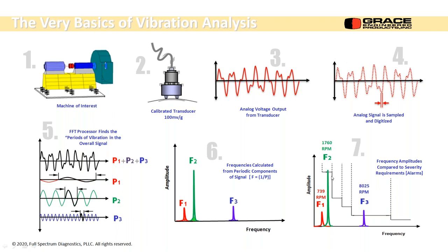If I know where 1 times RPM is, I can make my stair step pattern. And this we talked about a little bit last Thursday. This stair step pattern is giving me alarms on each frequency band. So I have a whole series of alarms now. We'll get a little more into that. So we're answering the question, how much is too much? If any one of these bands produces an amplitude that's above our limit, like this one or this one, we can go in and do some analysis and figure out what's causing that and how we can deal with it.